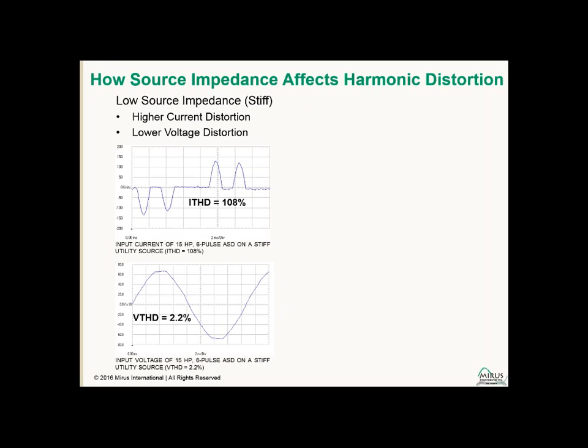So when a drive is supplied by a source, the actual current that variable speed drive will draw is dependent upon the impedance of that source. When you have a stiff source, which would be a large transformer with low impedance, so we have a relatively low impedance that the drive is being subjected to, that drive is going to draw very sharp pulses of current. And these sharp pulses contain high levels of harmonics.